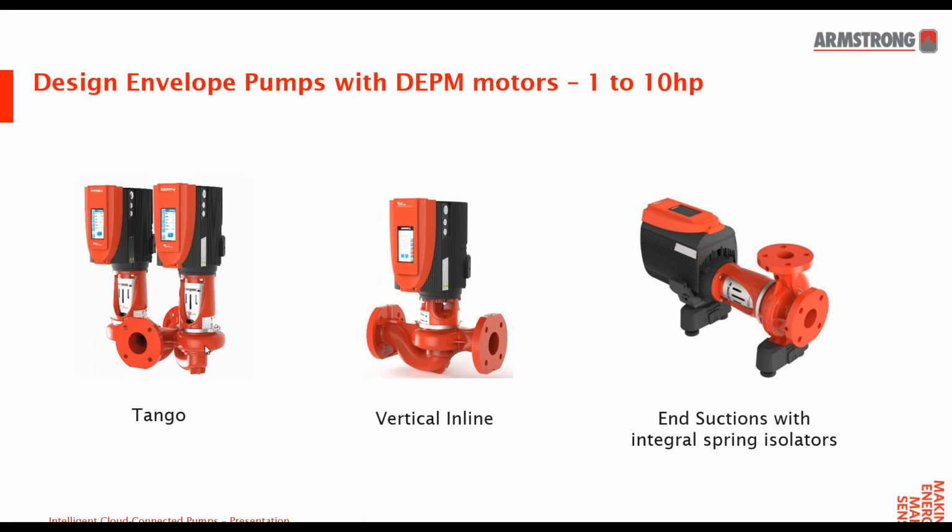So if, for example, it was 100 feet at the design point, and you install the DP sensor in the mechanical room, the DP sensor is going to give you 100 feet differential. Whereas with the sensorless control, you can just digitally enter any value you want for that, and the pump would move according to the map that it's programmed for.